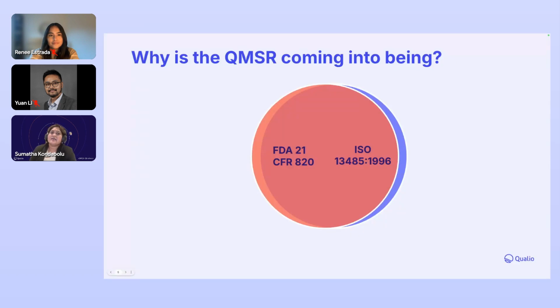So here you can see FDA 21 CFR Part 820, which is a widely adopted regulation that structures the quality management system of thousands of American medical device manufacturers. But it's also nearly 30 years old. When it launched in 1997, FDA 21 CFR Part 820 borrowed from many aspects of ISO 13485:1996 and was largely identical.